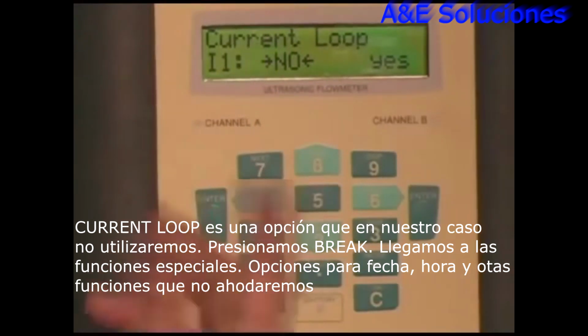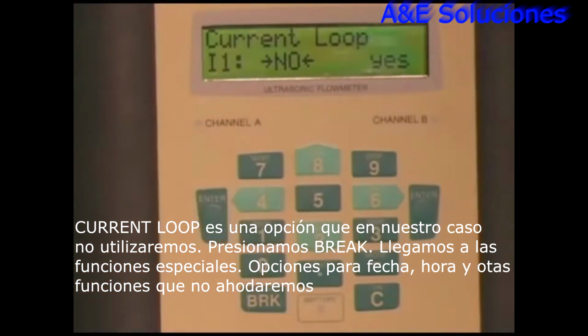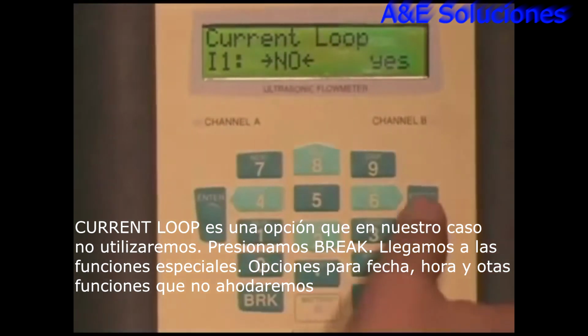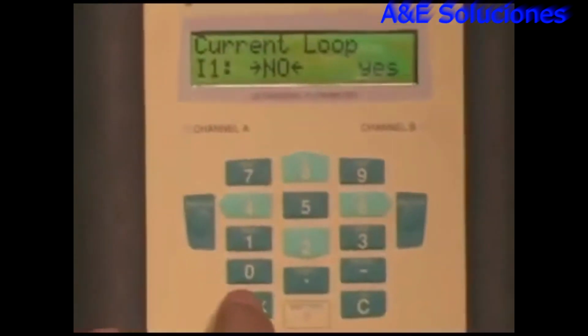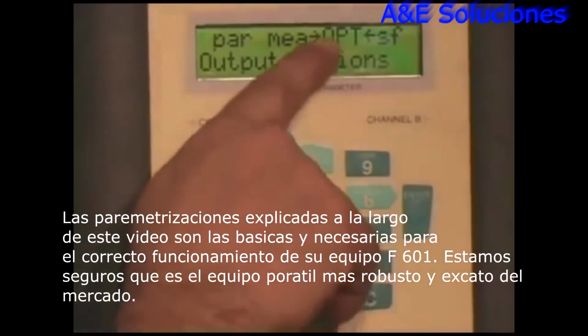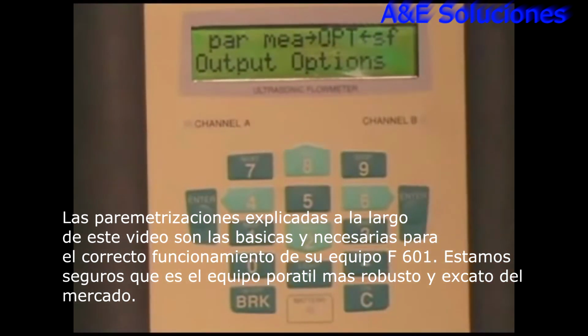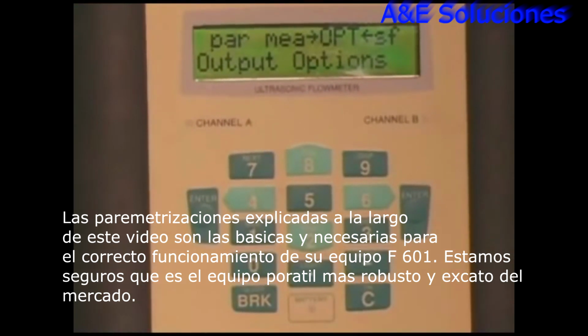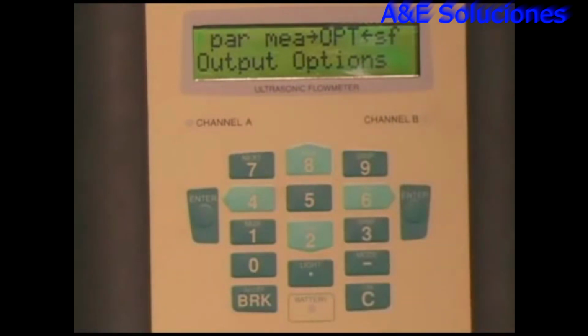Current loop, yes or no. On the bulkhead, we have 2 current options, and we can output current for flow. Let's say, for example, if we turned it on, it would ask us what we want to set the maximum to and the minimum to. So that's pretty much it as far as the options in the meter. We hit the break key. Our special functions over here contain things like setting up the clock time, the storage, deleting the data that's been stored, parameter storage. We can save up to 14 different sites, pipe sites, and we manage that in the special functions.